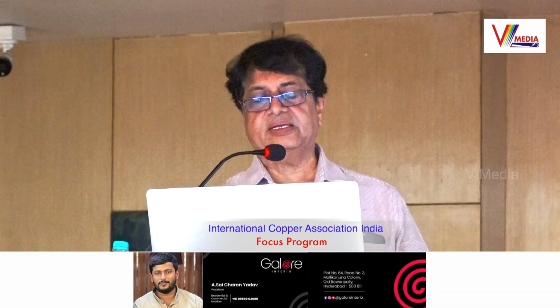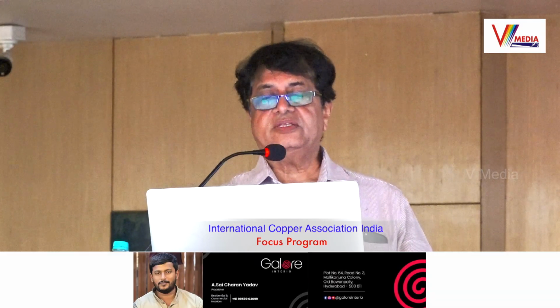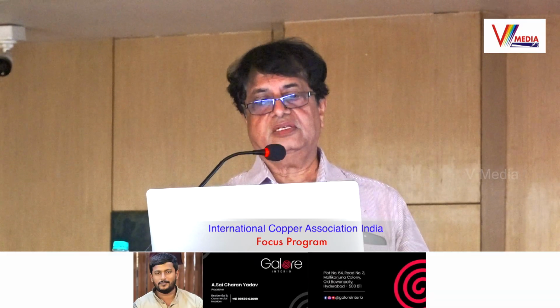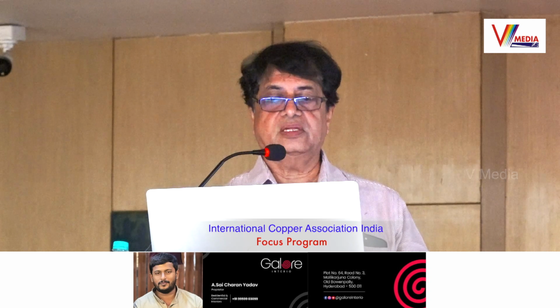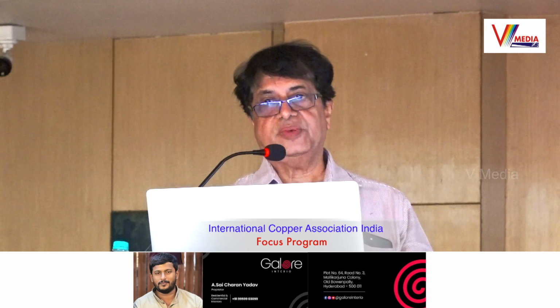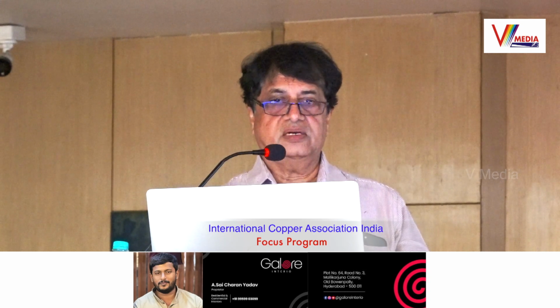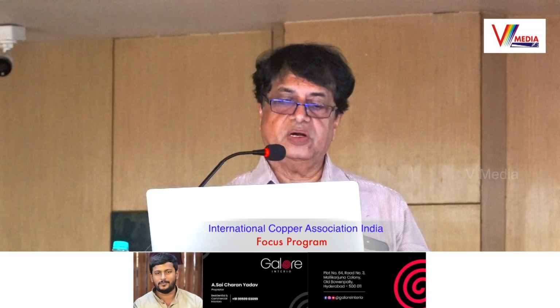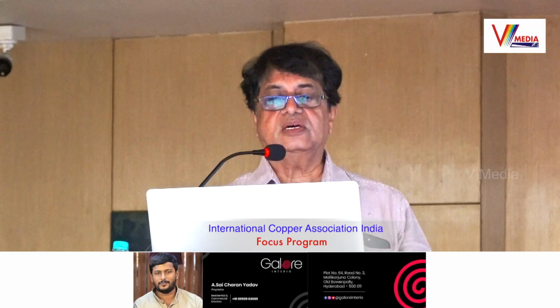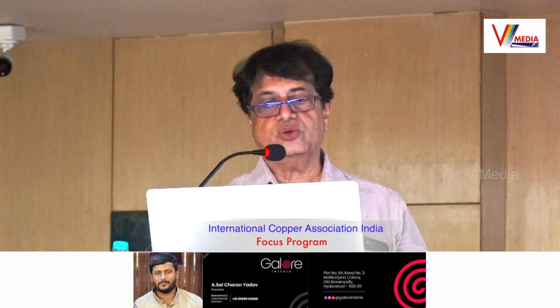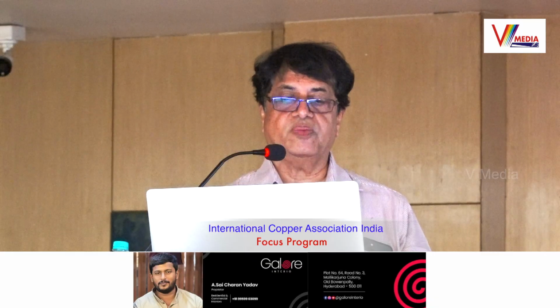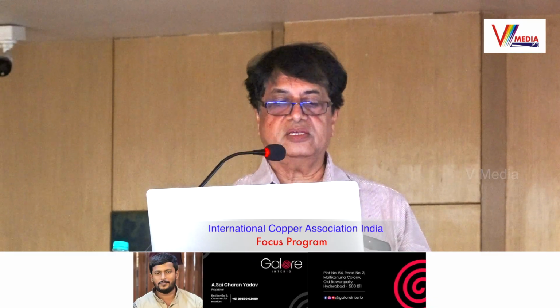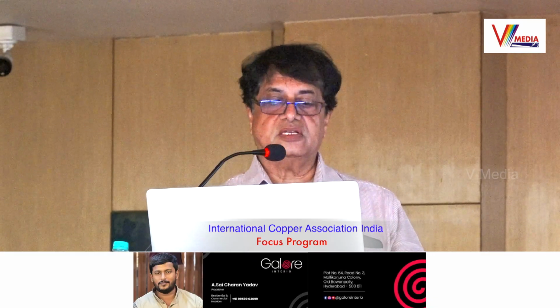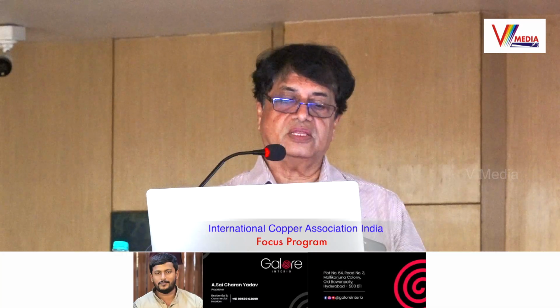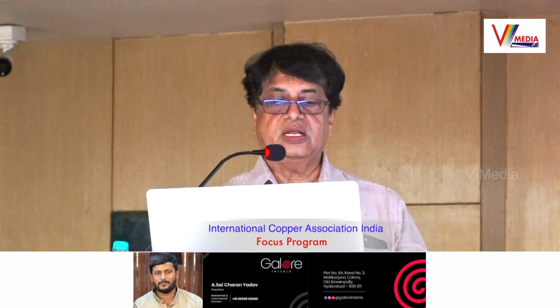Nowadays for high-rise buildings, the complete building structure, the RCC reinforcement, is earthed, and for that certain requirements are there. The bars are earthed, and at the foundation level, certain earth grids are required to be made. These points should also be considered at the time of planning. If such earthing is going to be done, then the requirements related to it should be taken from your electrical consultant.